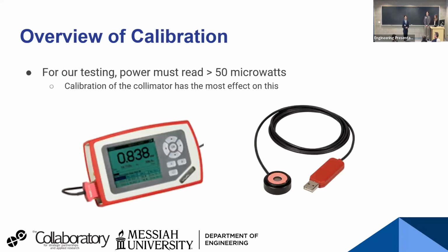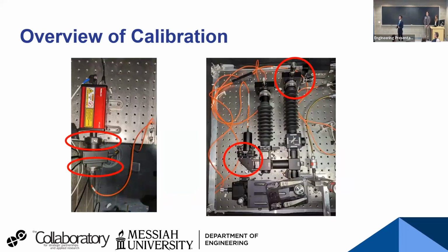To be able to conduct this testing, we need to calibrate our optic system. A fully calibrated optic system will have a laser power of at least 50 microwatts to be able to conduct any reasonable test. To make sure that we reach this threshold, we use a power meter to evaluate the power output of the laser at all points in the system. We have recently reached this threshold and gone above it, but let me tell you about how we got to that point. So with calibration of the optic system, we have 4 areas in the optic system that need to be correctly calibrated or aligned. In these 4 areas, there's a total of 15 screws or adjustment knobs that need to be reasonably calibrated to get a functional optic system.